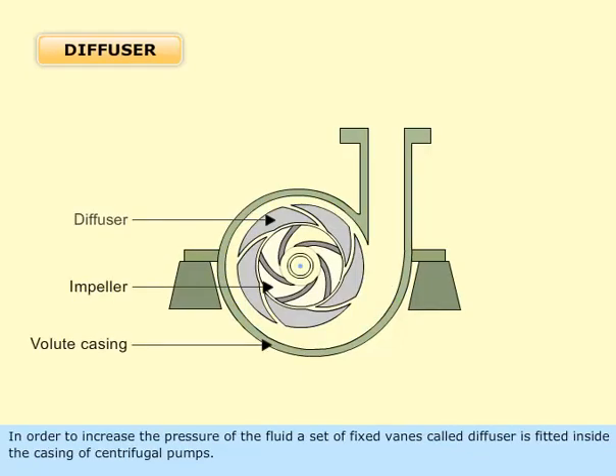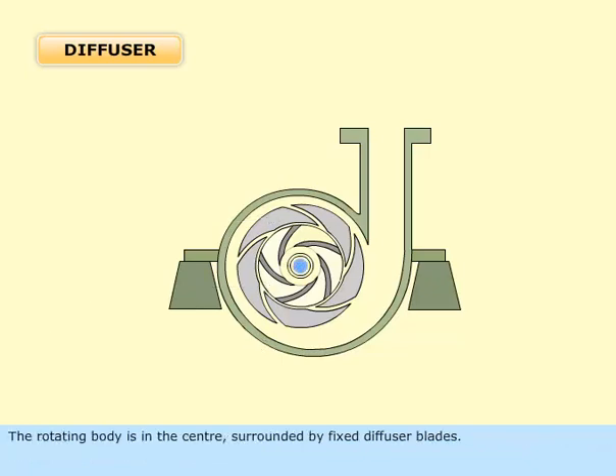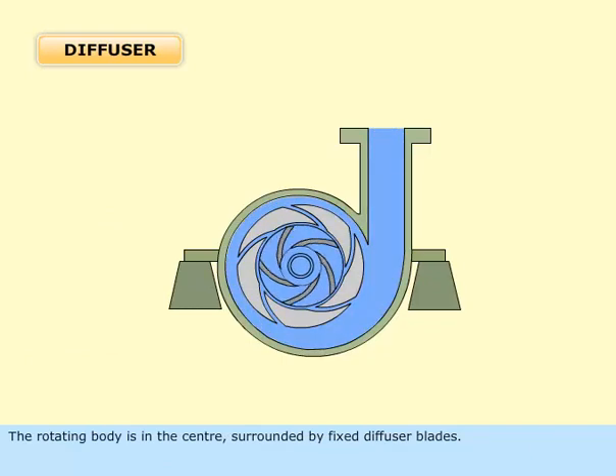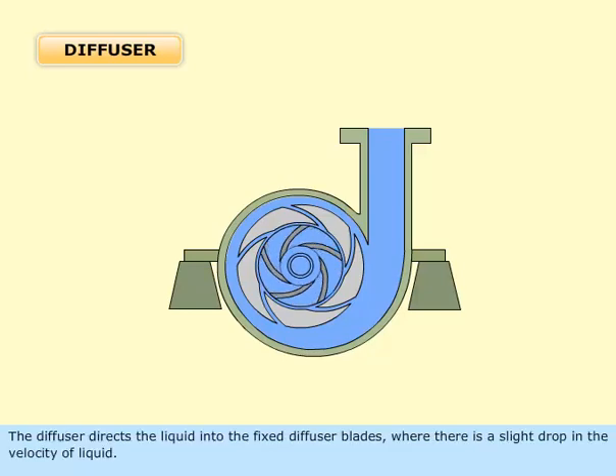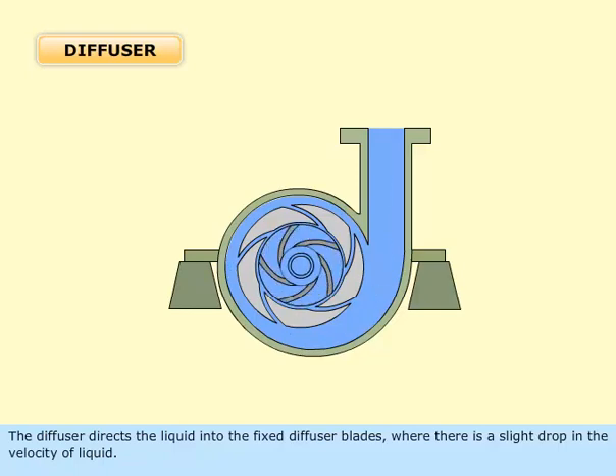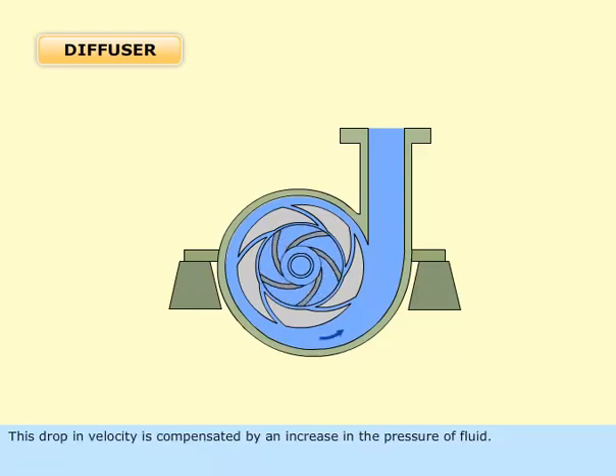In order to increase the pressure of the fluid, a set of fixed vanes called a diffuser is fitted inside the casing of centrifugal pumps. The rotating body is in the center surrounded by fixed diffuser blades. The diffuser directs the liquid into the fixed diffuser blades where there is a slight drop in the velocity of liquid. This drop in velocity is compensated by an increase in the pressure of the fluid.